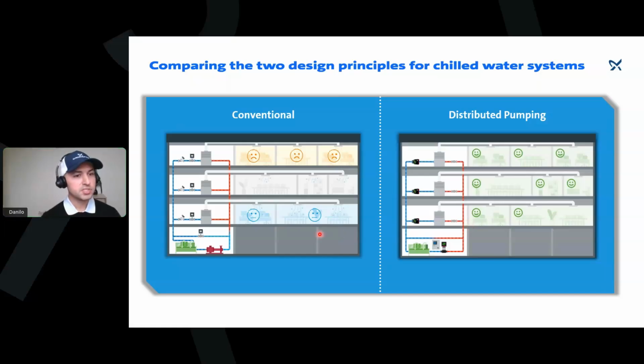So the idea of distributed pumping is that we want to eliminate those valves and those throttling valves, because basically what those valves are delivering to you is just more pressure for your pumps, right? All your pump has to do is overcome the pressure, the head generated by those valves. The metaphor we usually like to mention in this case is that your pump is the gas and your valves are the brake, right? You have one foot on the brake and the other foot on the gas. You're pumping while you're braking at the same time.